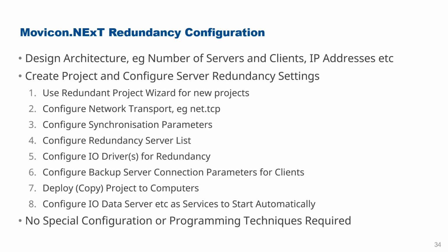For redundancy configuration, the process to use is here. First of all, you need to design your architecture. You need to consider how many servers and clients there are. You need to do your IP address mapping. And once you've done all of that, you can then start to create your project. There is a redundant project wizard, but it's also possible to add redundancy to an existing application by configuring server redundancy settings. The first thing you do is configure your network transport.